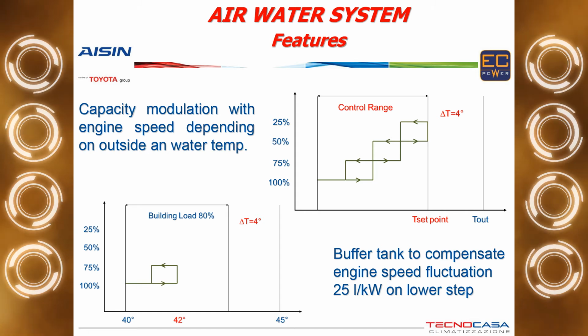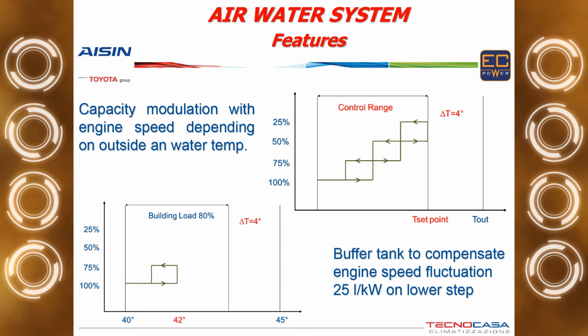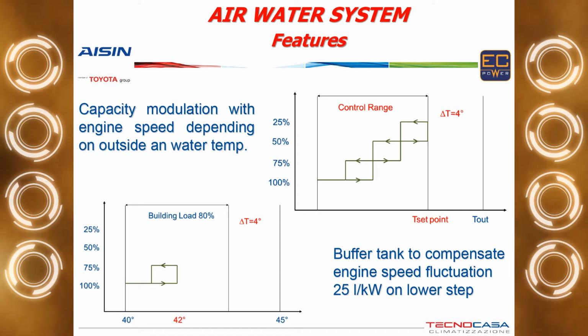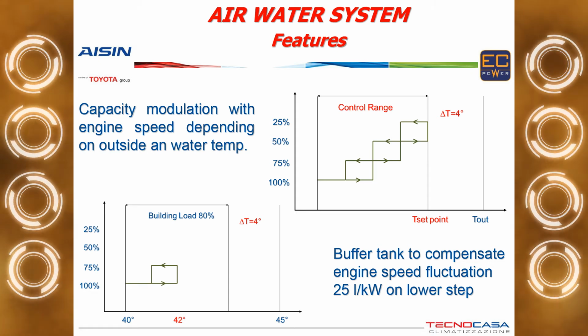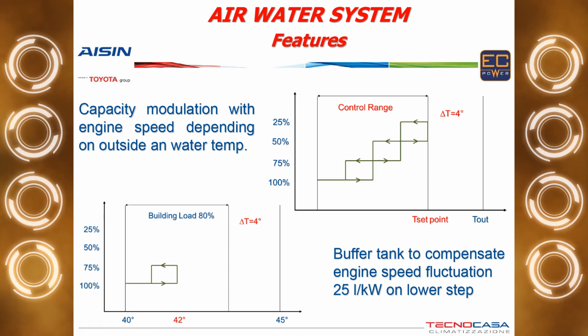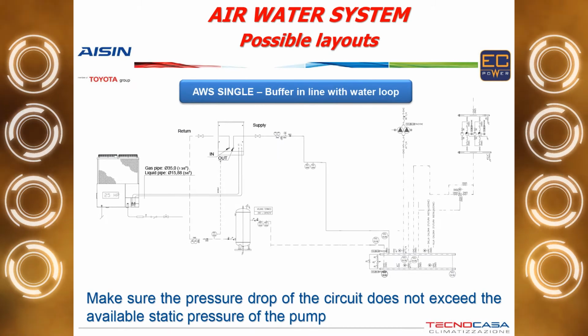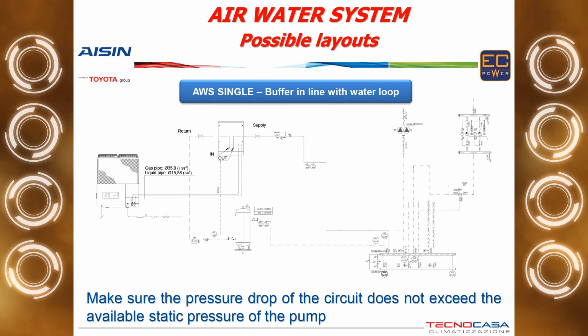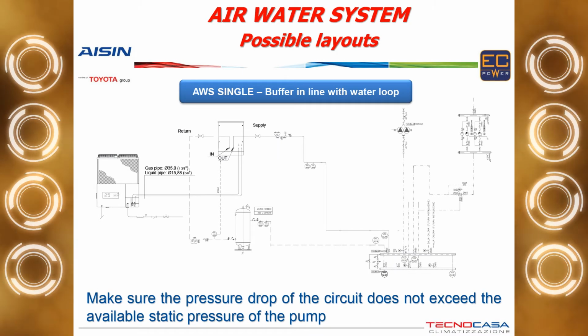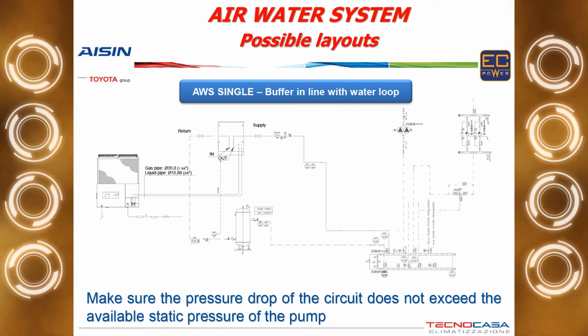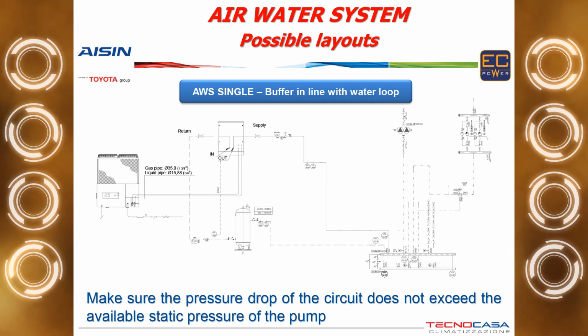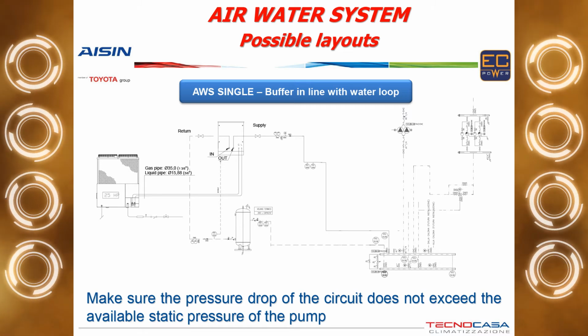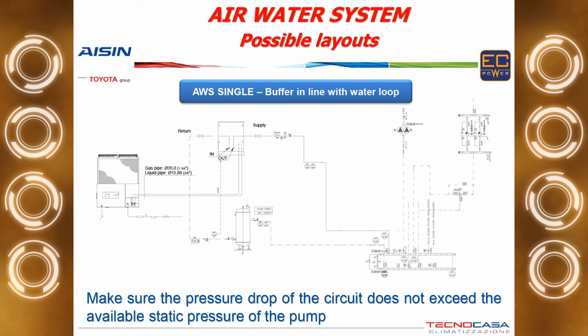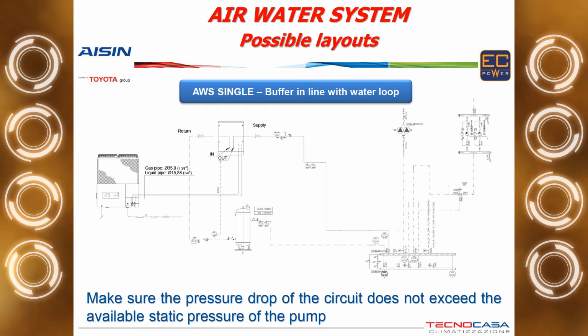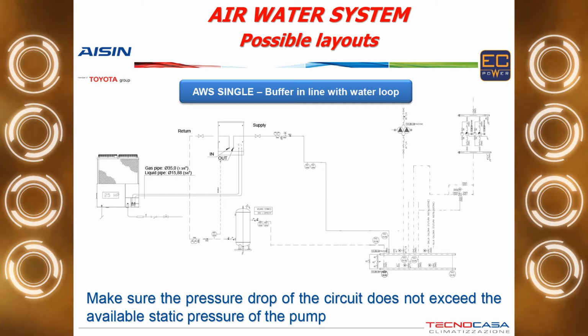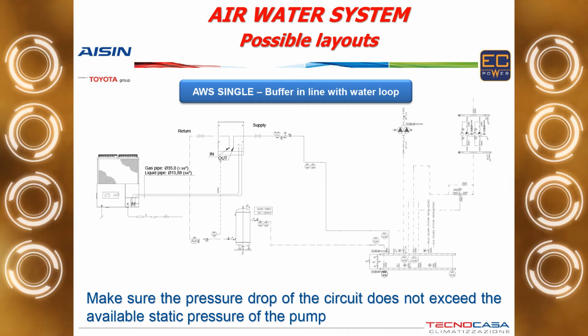This amount of water is, however, reduced, so we can save money if we compare this system to maybe absorption chillers, which need a large amount of water for the process and also for the cooling tower. Here you can see, for instance, one layout where the buffer is in line with the water loop. This is 1 GHP, 1 air-water system, single, and of course we have a distribution to fan coils and something also coming from low temperature underfloor heating.